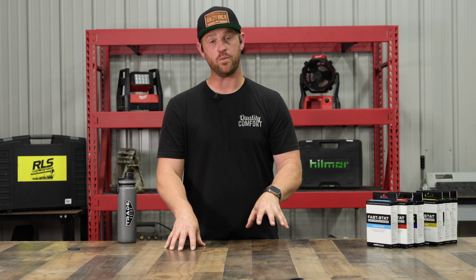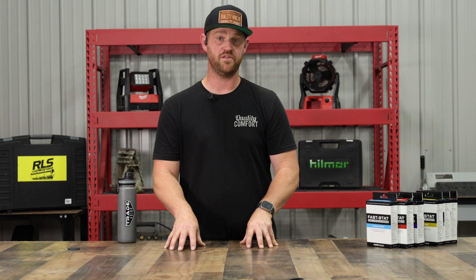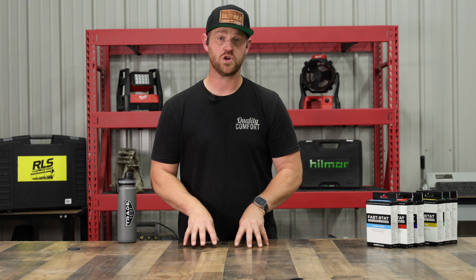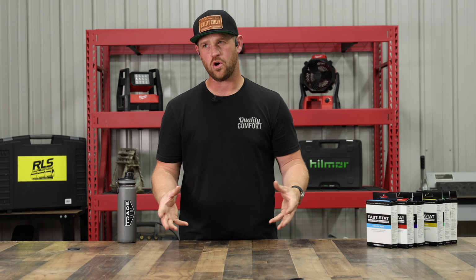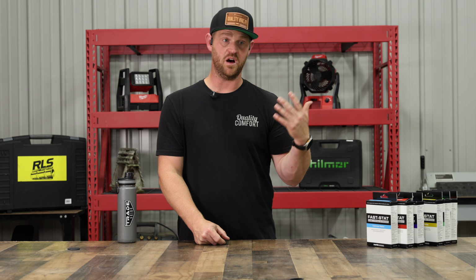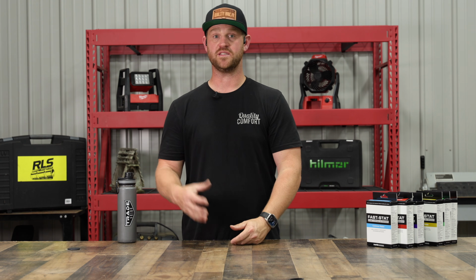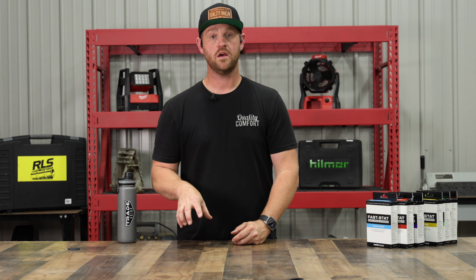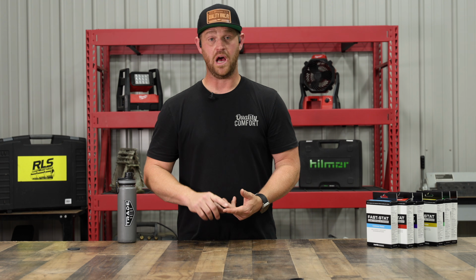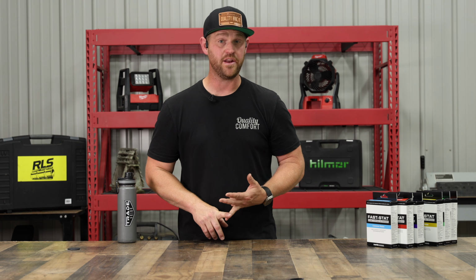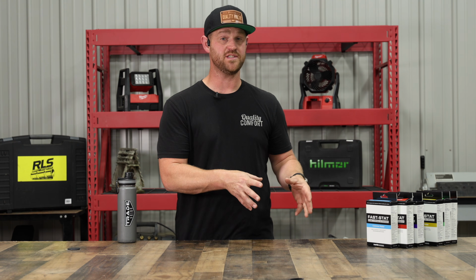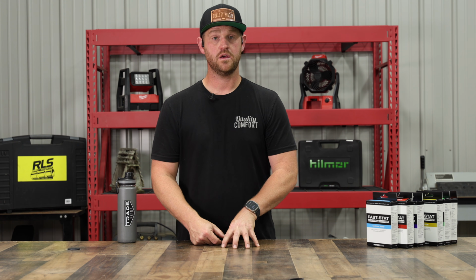But you want to make sure that return duct is large enough. It's not necessarily a huge hurdle, but just something that you want to be aware of whenever you're going through the process of doing your estimate, because if they need to increase that duct, you need to make sure, is it possible? How are you going to do it? Are you needing to add a return maybe, or just increase the size of the one that's already there? But that's definitely something you need to be looking at.